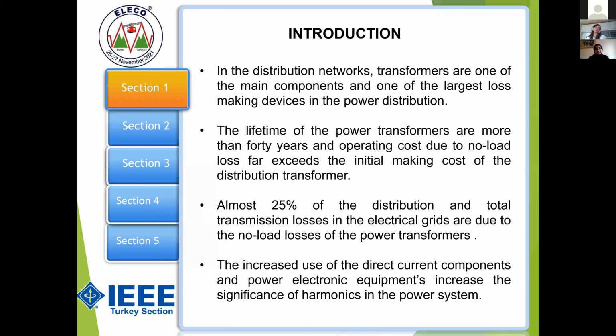As we know, the transformer is a very important part of the distribution and transmission system. In the distribution system, the transformer is one of the major components. The normal age of a transformer is more than 40 years. Generally, I can't say more than that, but it is normally 40 years. And the operating cost due to the no-load losses or core losses can exceed the initial cost of the transformer, so we must take care of the no-load losses. In some cases the transformer doesn't work, but no-load loss is always there. Almost 25% of the distribution and transmission losses in the electrical grids are due to the no-load losses of the transformer.